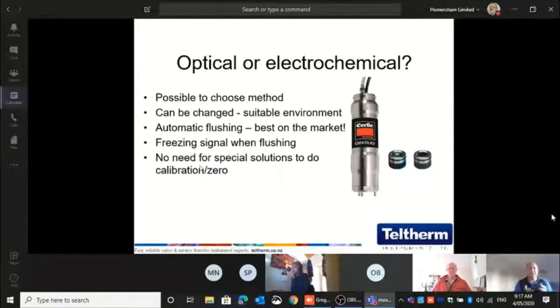The advantage, like you saw this morning, is you can unscrew the cap here and just pop out the sensor and plug in another sensor. Doesn't matter if you've got optical or galvanic. Very easy to do. At the moment we normally supply a galvanic cell as standard, but if people want an optical, absolutely not a problem.